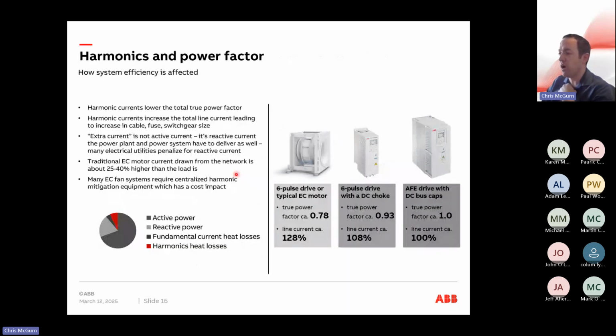When it comes to these harmonics, the focus tends to be on motors and VSDs, because they tend to be the high-load equipment in buildings that cause the majority of the harmonic impact, because they could be drawing high kilowatts. They could be drawing, like I say, 300 kilowatts, depending on how your system is set up. Whereas LED lighting and televisions and whatever else tend to be relatively low. So VSDs and motors are the first place that energy consumption experts will look whenever they're trying to improve this.